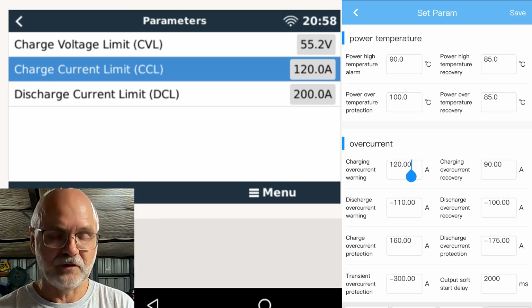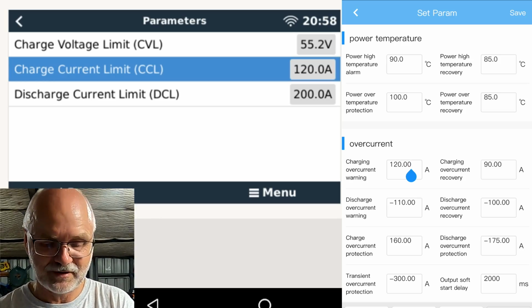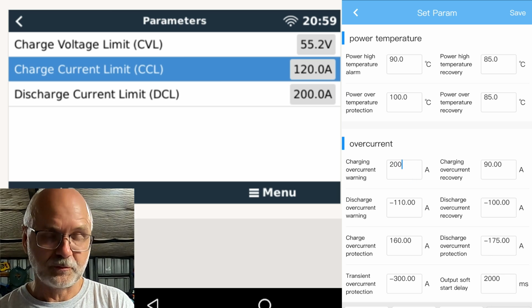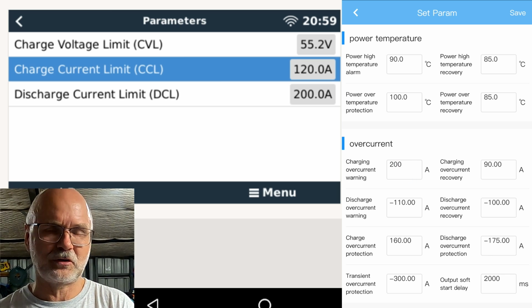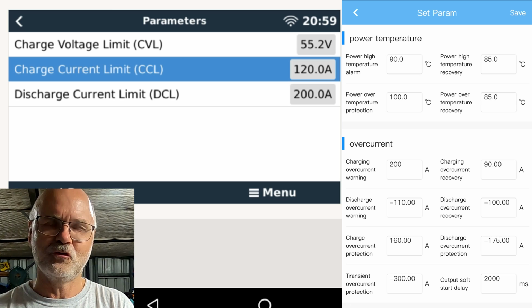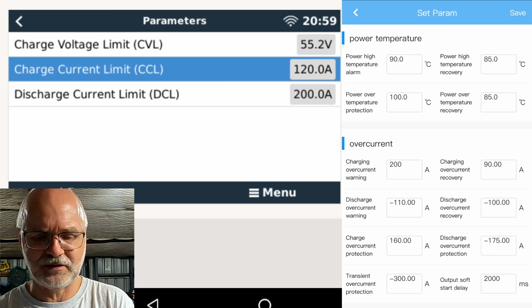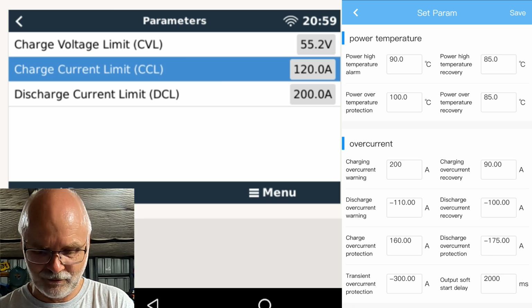Interestingly, if you connect now to the slave battery via the computer and change the same setting in there, it won't have any effect in the Victron system. So only the master BMS determines what is being reported to the Victron system. All the settings in the slave battery will be completely ignored. So if you want a maximum charge current of 200 amps, we can set 200 amps in the parameter, because 200 divided by 2 times 2, because 2 batteries, is 200, right? So if we save this one, we will see it increasing to 200 amps now.